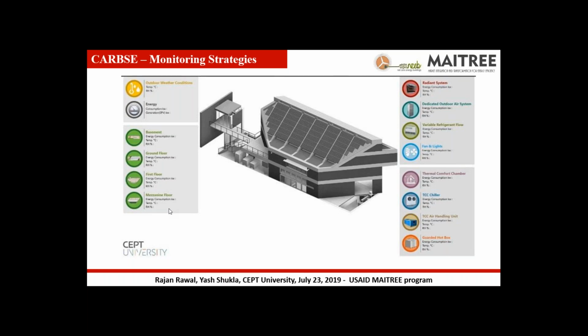On the right side, you'll see two other blocks for the other two systems. The top one on the right side shows the radiant system, dedicated outdoor system, VRF system, fans and lights. So you will see what the air conditioning systems' and the fans' energy consumption is instantaneously at that time during the day.